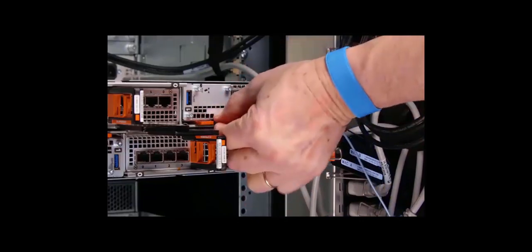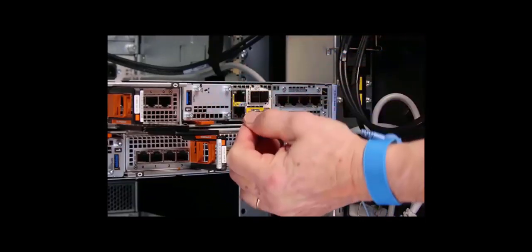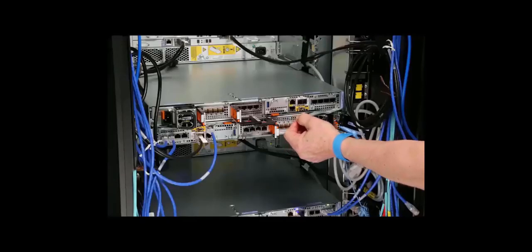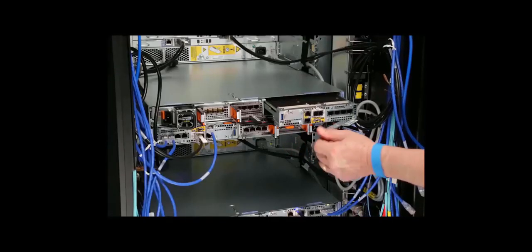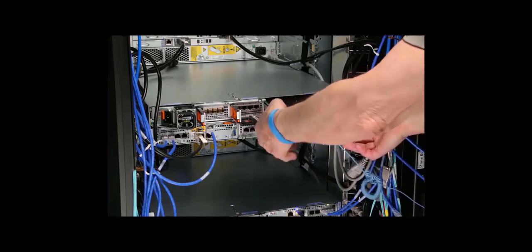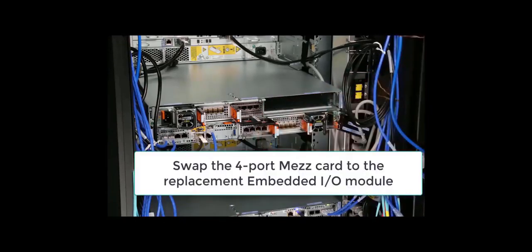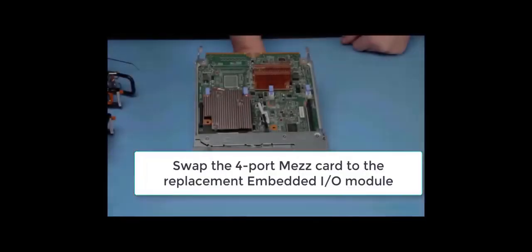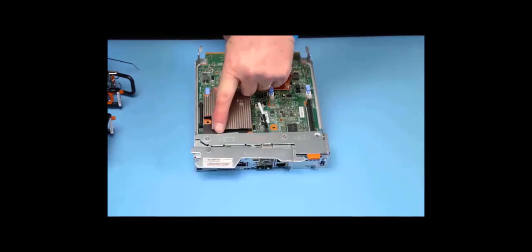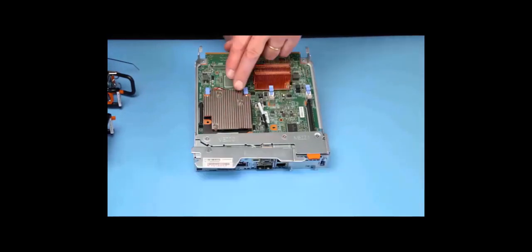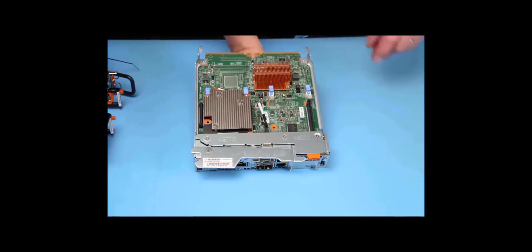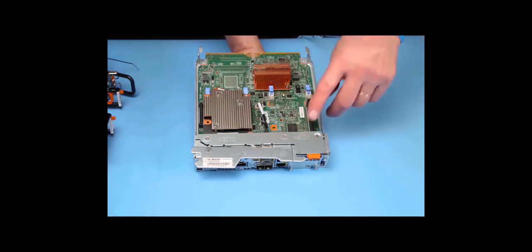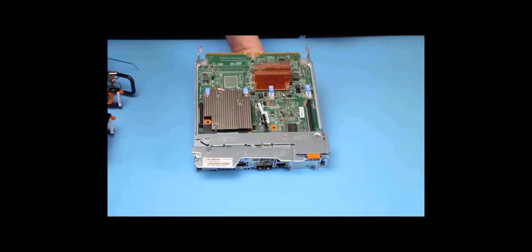You push in the orange tab and you're going to use the lever. You're going to ease that I/O module on out. Grab it by the side and go ahead and lay it on the table. And you want to swap the 4-port MEZ card. You see here, this is MEZ 0. That's a 4-port card. There is another MEZ port here. You see MEZ port 1. There's nothing in that board.